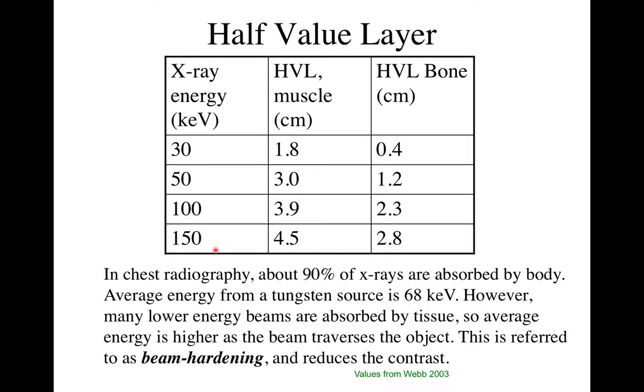Here are actual numbers — this is energy dependent. For muscle and bone at 50–100 keV, which is our clinical imaging range, it's about 3–4 cm half-value layer for muscle and 1–2 cm for bone. So 50% of those photons will be gone in that distance.